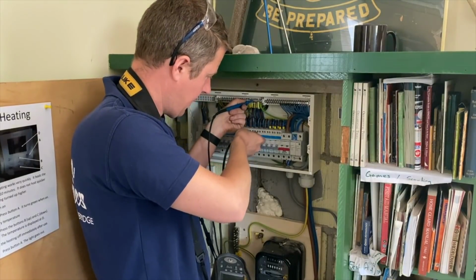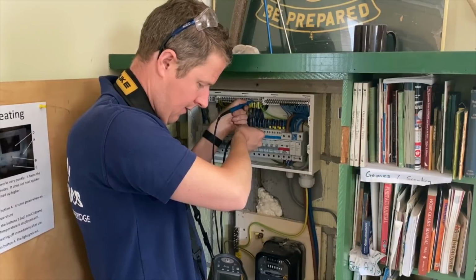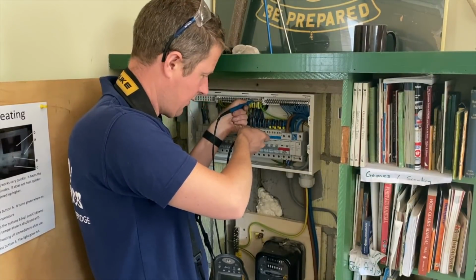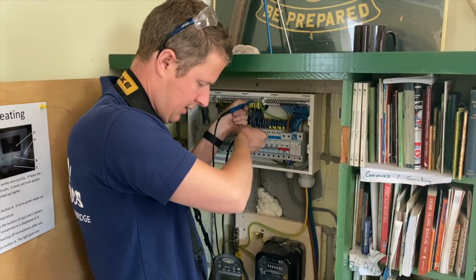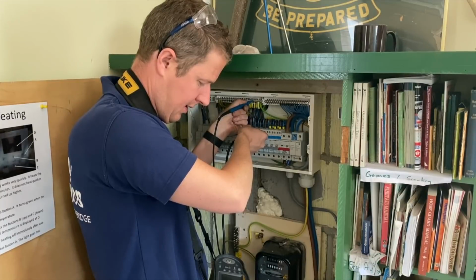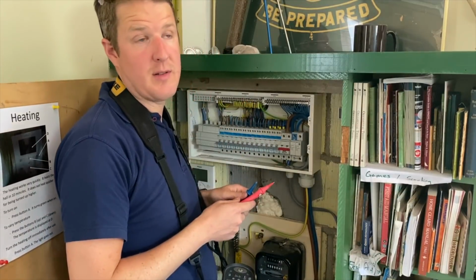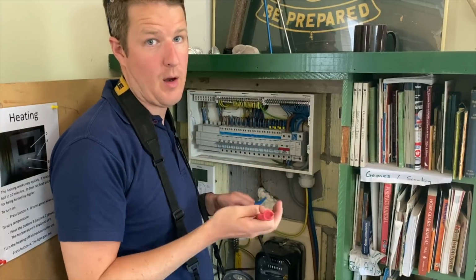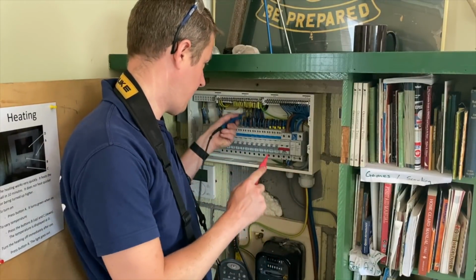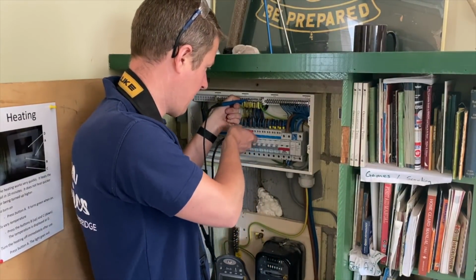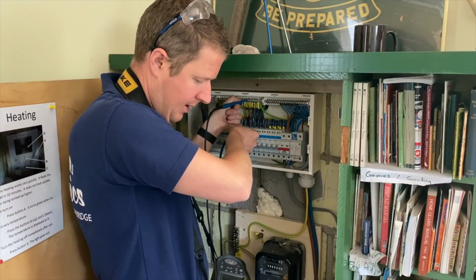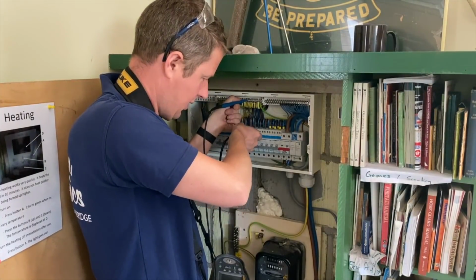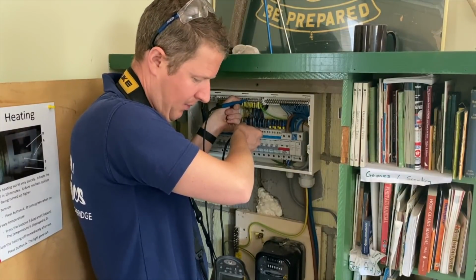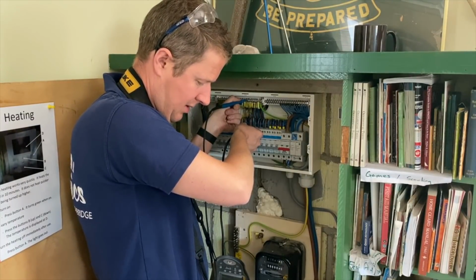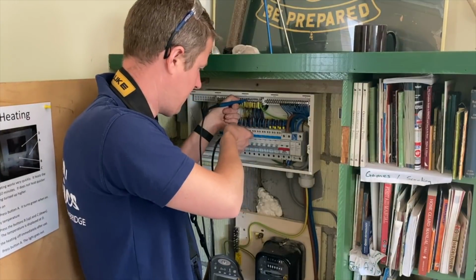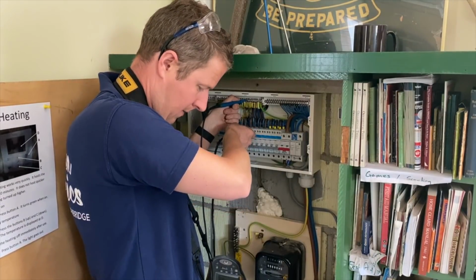So on this circuit we've got phase to CPC 200 megohms, but neutral to CPC is a little bit lower, 22.6 megohms. Still acceptable because the readings should be over 1 megohm. So that's still fine, but something to think about. If a circuit is close to the borderline, then I would usually do some investigation, but if it's up in the 20s, like this one's in the 20s as well, it's probably due to just some connected equipment.